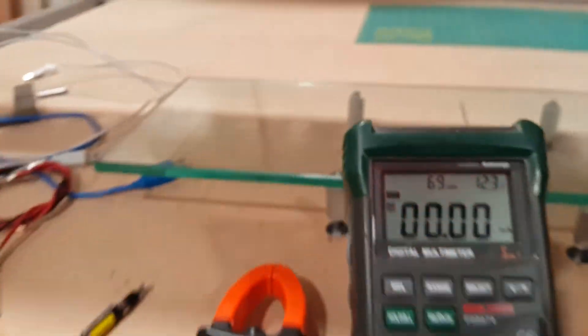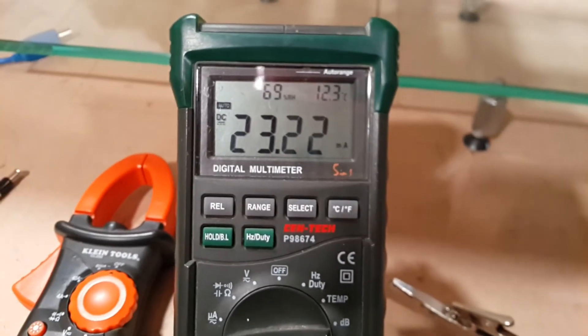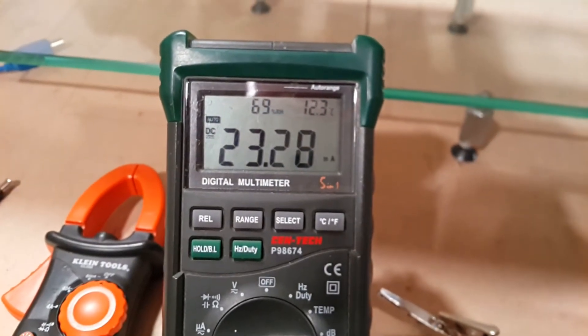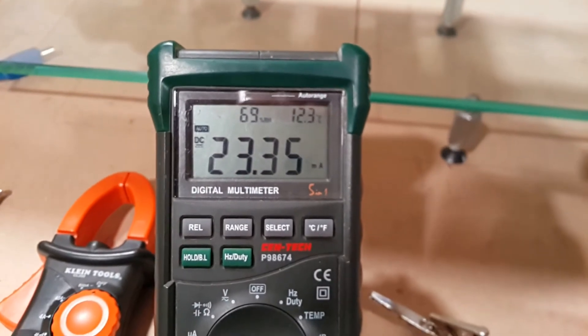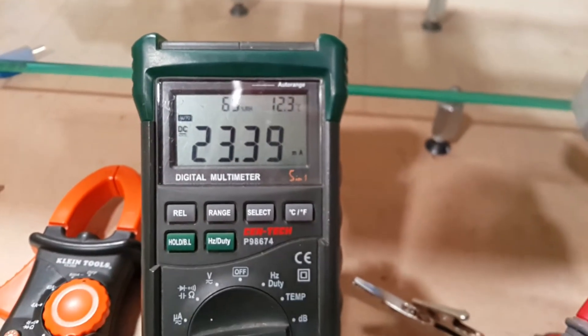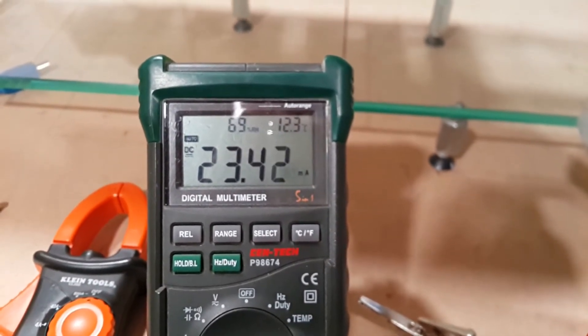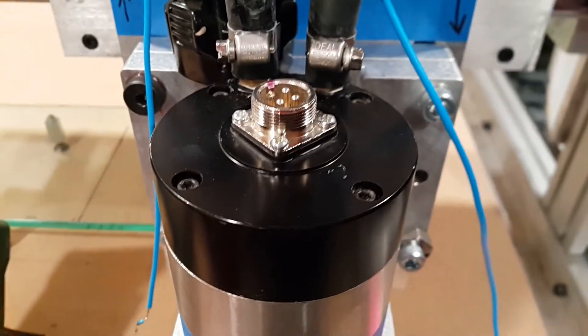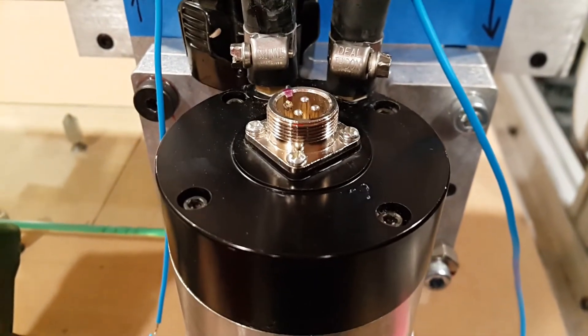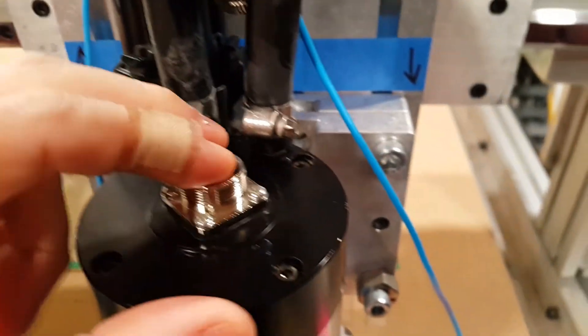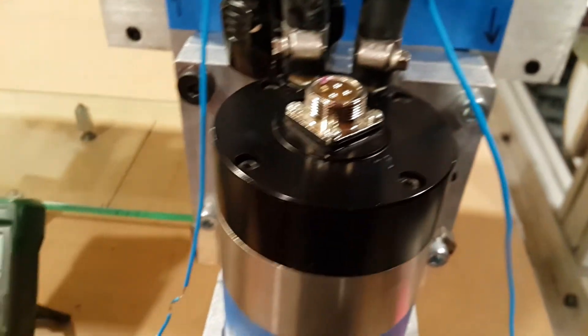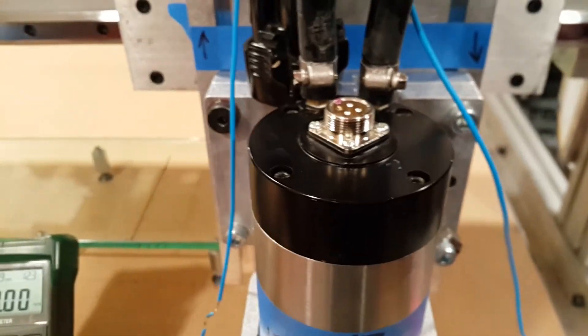It's basically the amount of current that's flowing through that 500-ohm resistor, so it's about 23 milliamps. We're going to use that current to go through one winding at a time and then measure the voltage drop, and that should allow us to calculate the resistance of each winding.